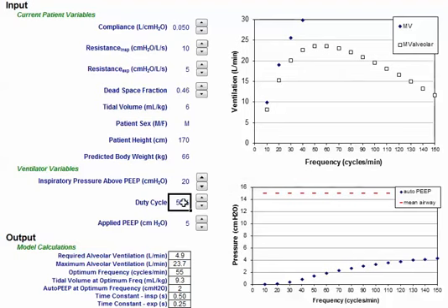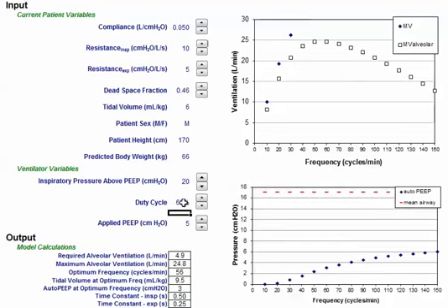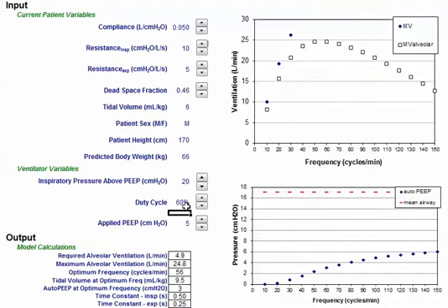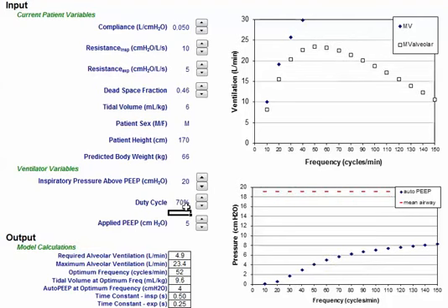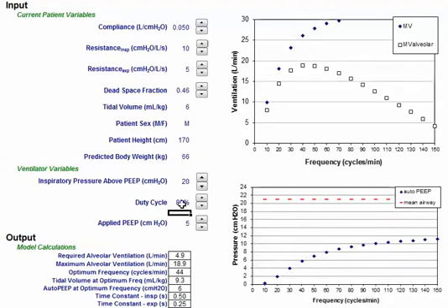I'm going to change my duty cycle to 60%, making it an inverse ratio. As you notice, I'm obtaining more minute ventilation. Let's change that to 65% — didn't really gain much more. Let's go to 70%. So around 60% was my max. If I go to 80% and make it more inverse, I'm not gaining anything else — I'm actually dropping my tidal volume.